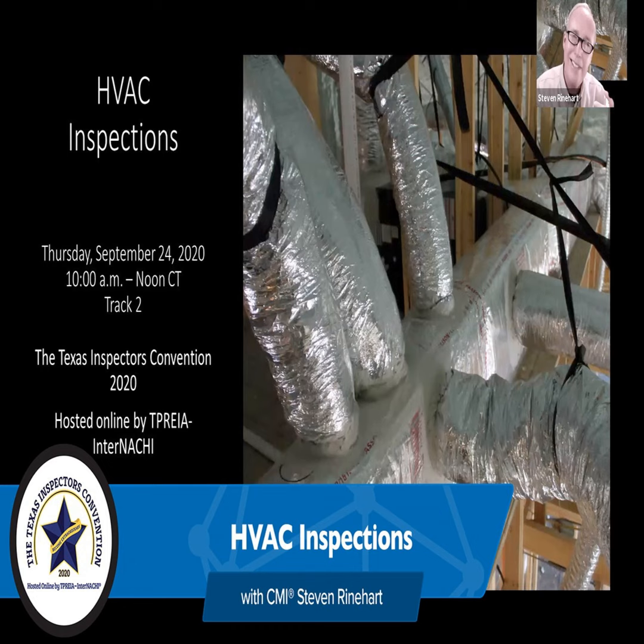And I've talked with the client and said, hey, we might recommend having an HVAC guy look, with the thought that maybe all the heat strips aren't working. Some of those older Rheem electric units, it's real easy to open up that electrical compartment and just look. I typically do, because it's not uncommon, if they've been there a long time, to see burned wires. You'll see the wires to the heating strips, and then the over temperature sensors, and you look for burned wires.